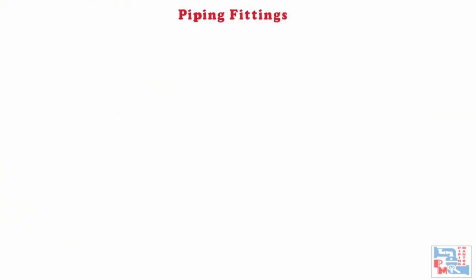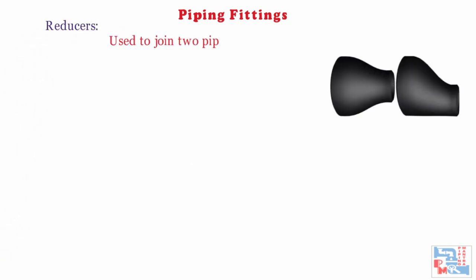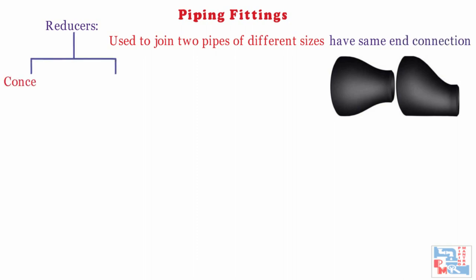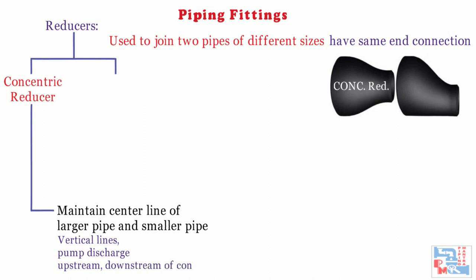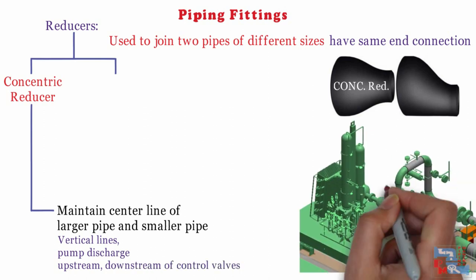Reducers are widely used fittings to join two pipes of different sizes having the same end connection. There are two types. First is concentric reducer, commonly denoted as CONC reducer in isometrics and P&IDs. It is used when we need to maintain the same centerline elevation for both the larger and smaller pipe. It is used in vertical lines, pump discharge, and upstream and downstream of control valves in some cases.